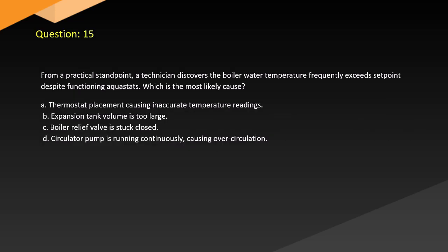Question 15. From a practical standpoint, a technician discovers the boiler water temperature frequently exceeds set point despite functioning aquastats. Which is the most likely cause? A. Thermostat placement causing inaccurate temperature readings. B. Expansion tank volume is too large. C. Boiler relief valve is stuck closed. D. Circulator pump is running continuously causing overcirculation.